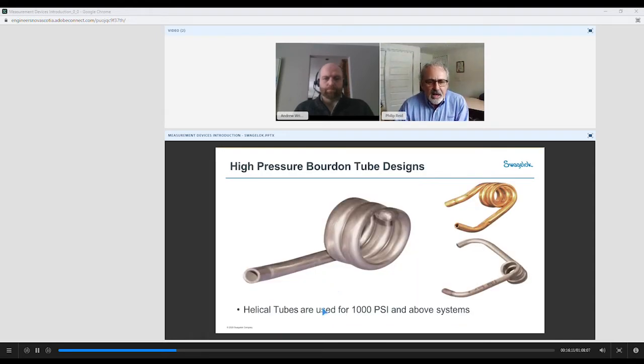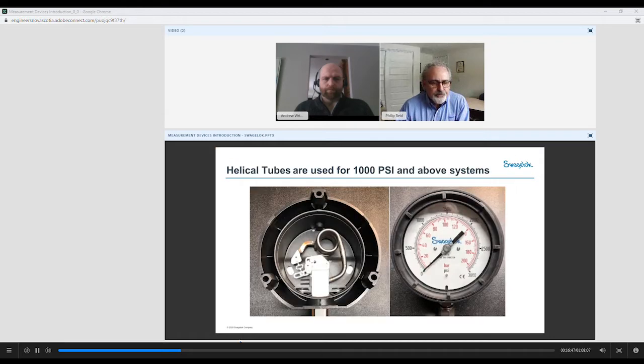Moving on a little bit, if we have pressures over 1,000 psig in a Bourdon tube type gauge, we will use a coiled Bourdon tube. And again, it's stiffer. This one you can see is at 100 bar. So, about 15 psi per bar. So getting into fairly high pressures, in that high pressure range, you will have a coiled Bourdon tube. And of course, the tubing wall thickness will be much thicker.